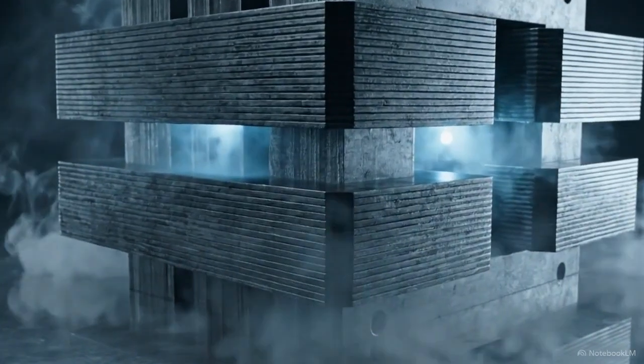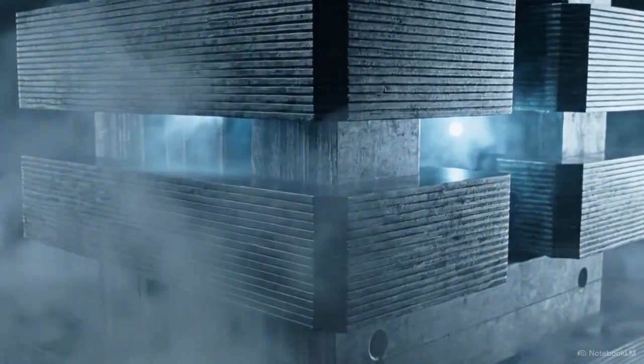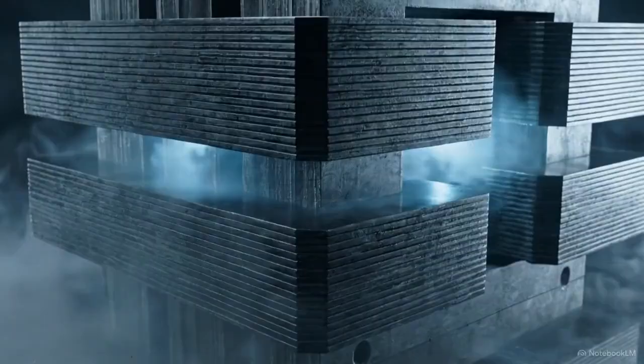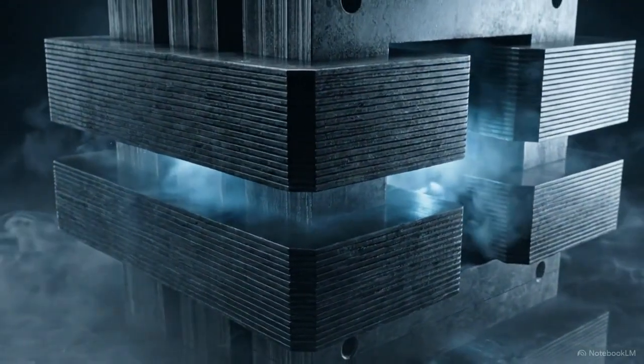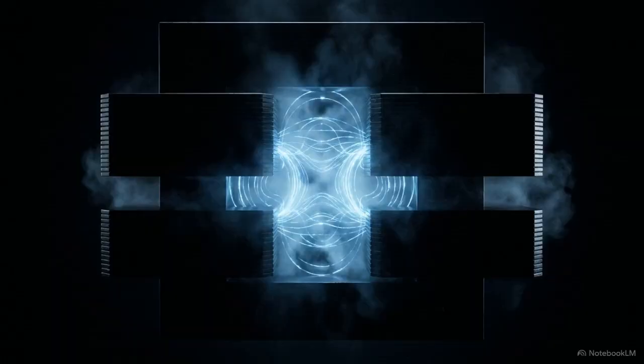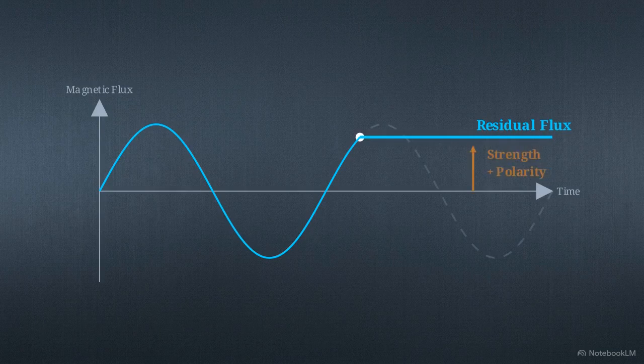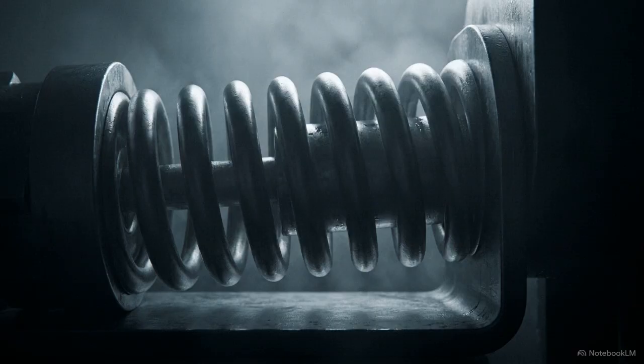a memory. Due to magnetic hysteresis, the heavy iron core holds a permanent magnetic signature even after the electricity stops flowing. Engineers call this trapped magnetic fingerprint residual flux. Its exact strength and polarity are locked in place, completely dictated by the specific millisecond the power was cut. A de-energized transformer behaves like a loaded spring, holding a silent, invisible threat within its core.